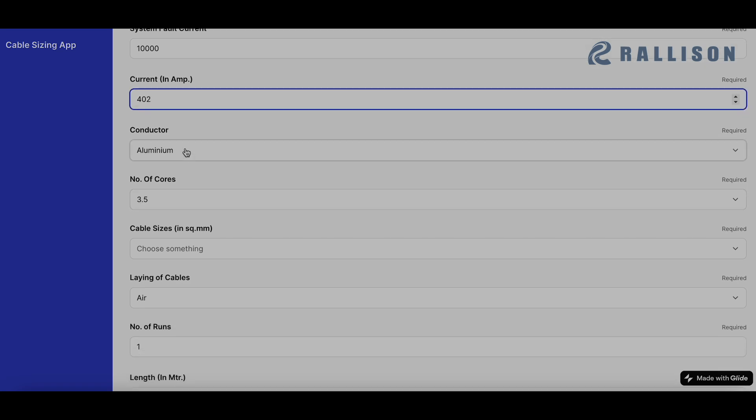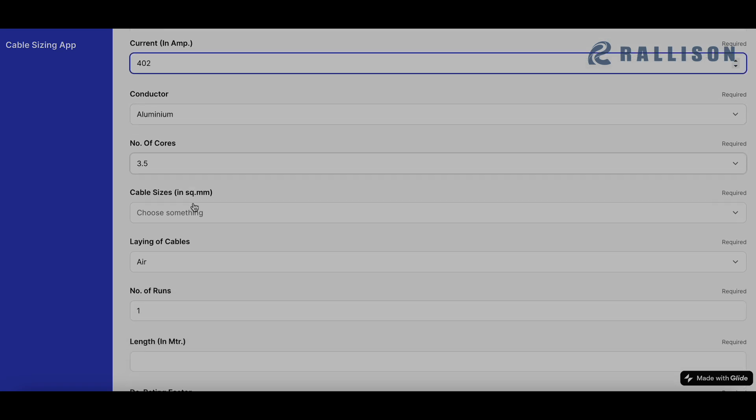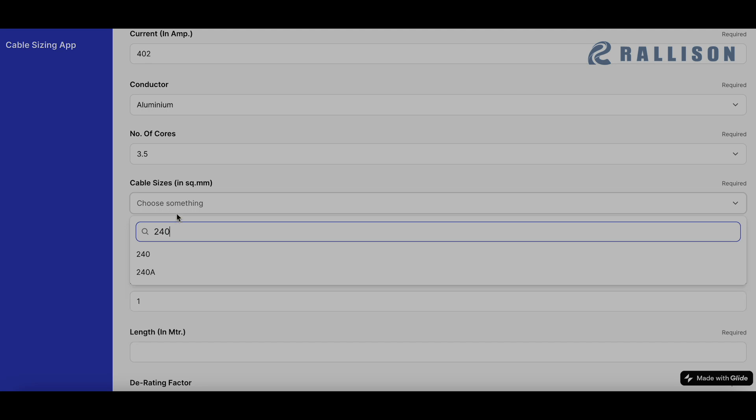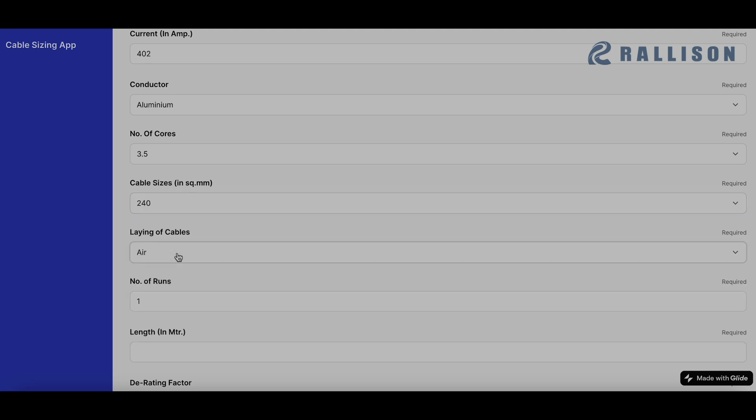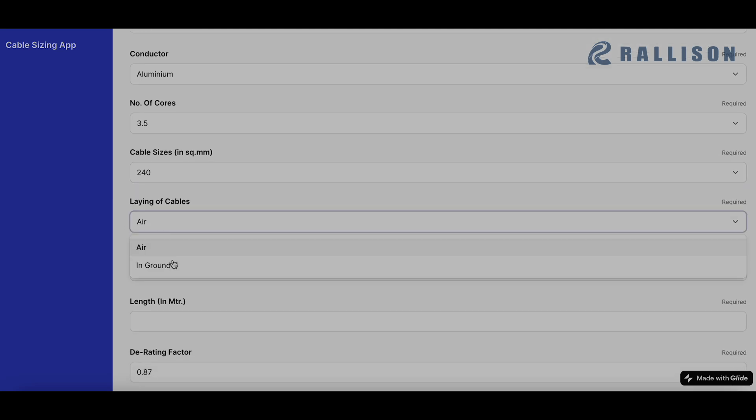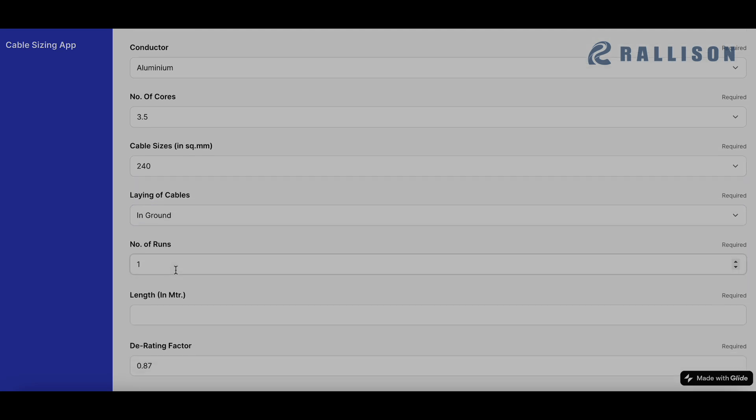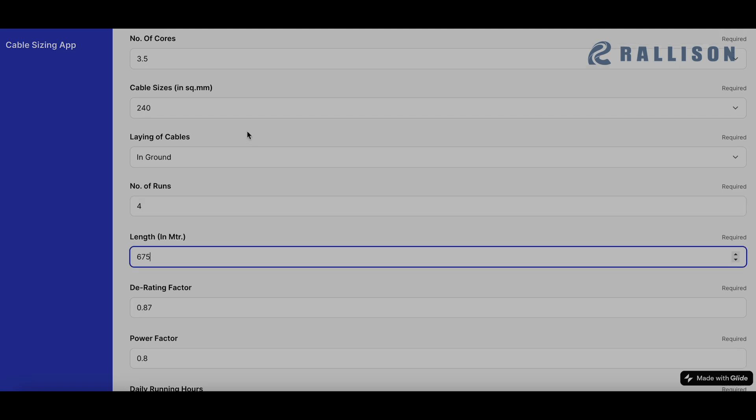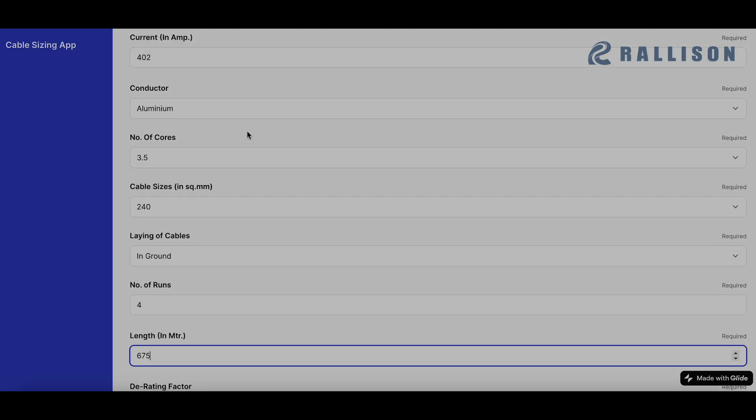We have chosen aluminium conductor, 3.5 cores and size for this example is 240 square mm. We'll be laying them in ground and total number of runs are 4. The length is 675 meters. All these values have essentially come from the design that we have chosen for this particular site and the design that we want to optimize.